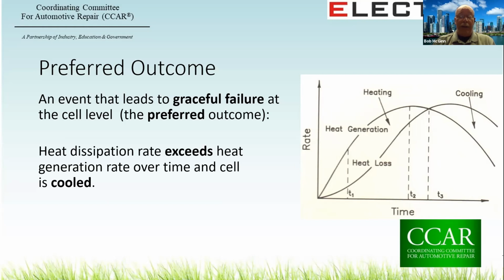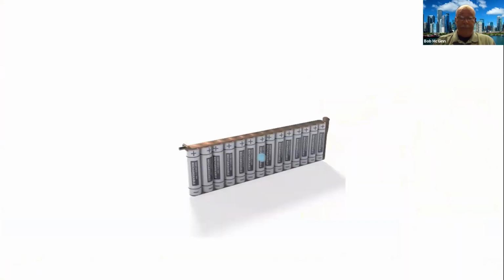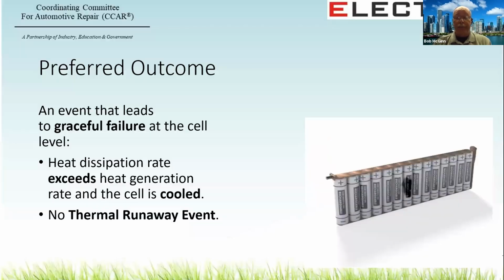It will look something like this. Think of the colors as a thermal scan. Really not much to look at. We scorched one cell. You may not even set a warning light in the dash. An event that leads to graceful failure at the cell level: there is an increase in temperature, a reaction occurs within the cell, and the heat dissipation rate exceeds the generation rate over time, or is approximately the same, and the cell is cooled.